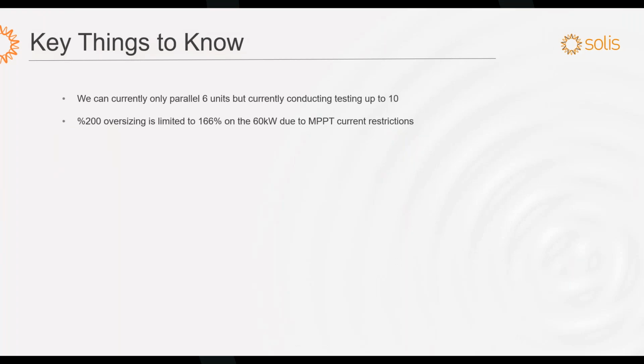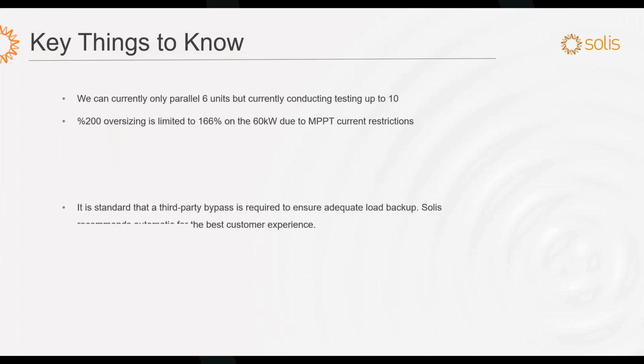200% oversizing is actually limited on the 60 kilowatt power class to 166%, and that's generally due to the MPPT current restrictions that we have with the product.